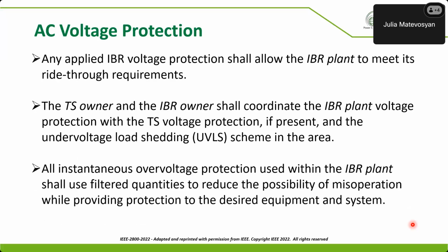All right, so then AC voltage protection. Again, any applied protection shall allow the plant to meet the ride-through requirements. If voltage protection is applied, then it should be coordinated with any equivalent protection that the transmission owner might have in the area, and obviously any undervoltage load shed scheme. The last bullet is important: instantaneous overvoltage protection used within the plant shall use filtered quantities.